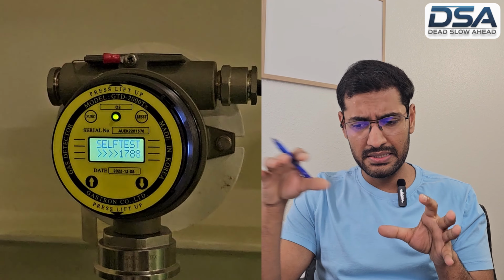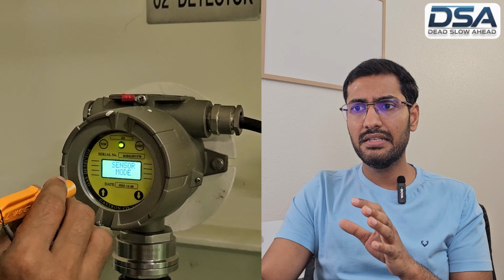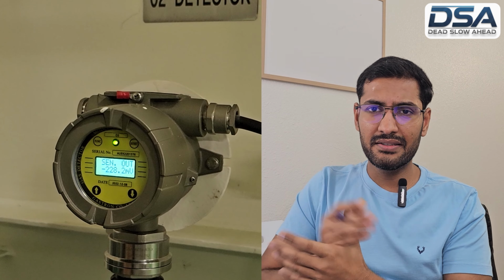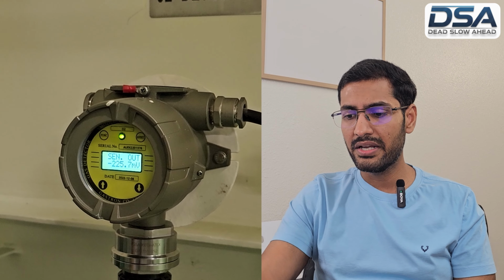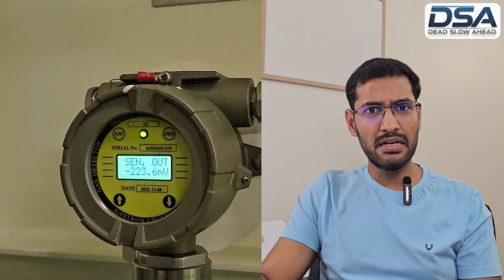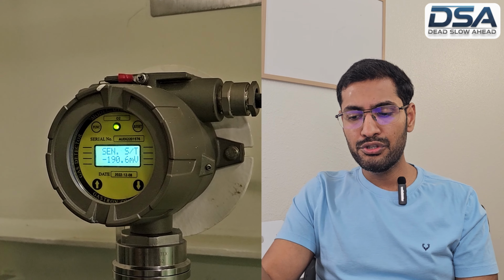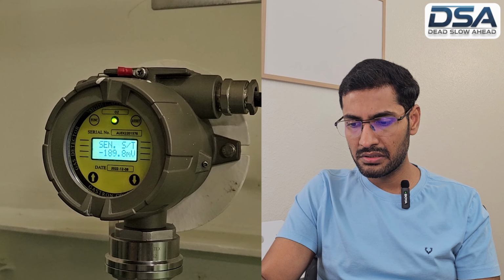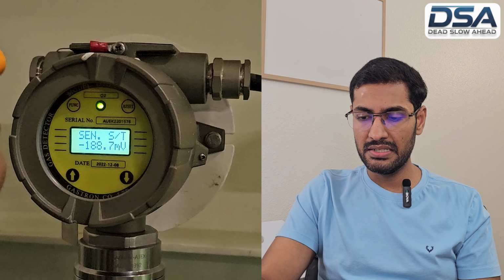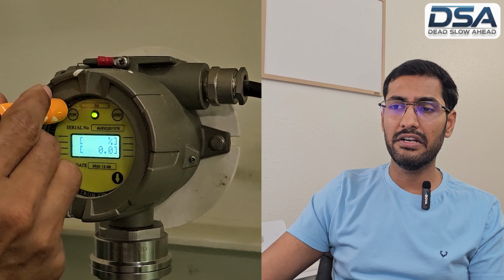In the meantime, the sensor does the necessary internal diagnostic checks, and once the self-test is over, we check the sensor output voltage, and in our case it was showing 228.5 millivolt. You can see the negative symbol before the numerical value; this is just a terminal indication, and you do not need to worry about it. We also checked the sensor ST voltage. It was around 190.4 millivolt, which is within our criteria and the normal range. This is basically a healthy sensor. So in this case you can run the diagnostic checks and verify the sensor condition.